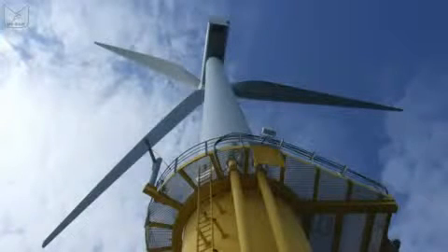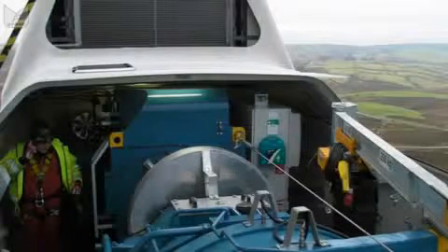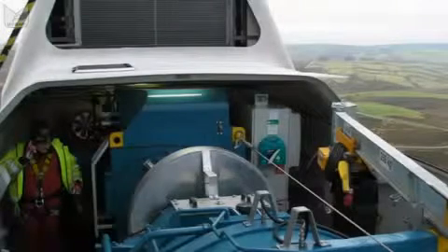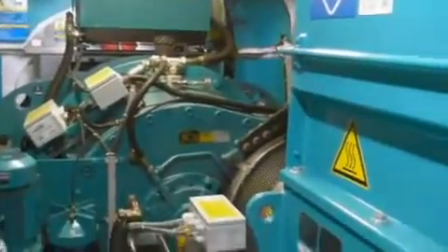The layout of a multi-megawatt nacelle is again more variable than for a smaller version. We always have to have a generator, but we may not have to have a transformer. In a few cases, such as the famous Enercon egg-shaped nacelle, we don't even need a gear box. They are direct drive, we just have a shaft linking to a generator, and then lots of extremely complicated electronics to condition that power for connection to the grid. But in most cases, we need the same as we needed in the small turbine. Gear box, generator, possibly a transformer, all in a fiberglass box.